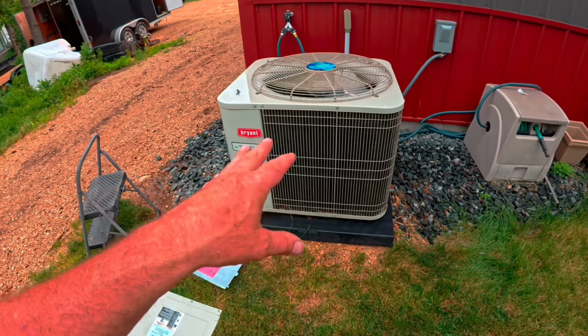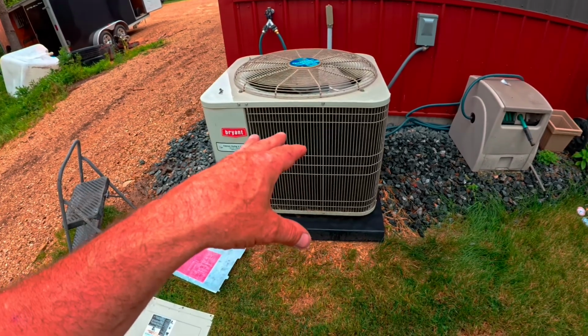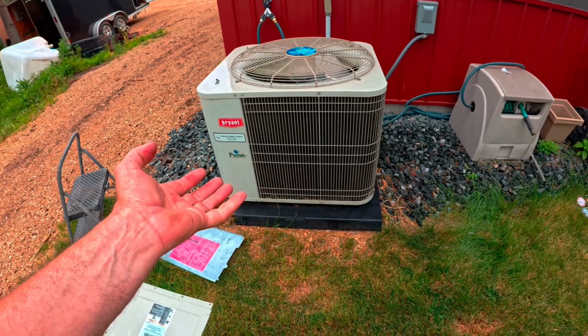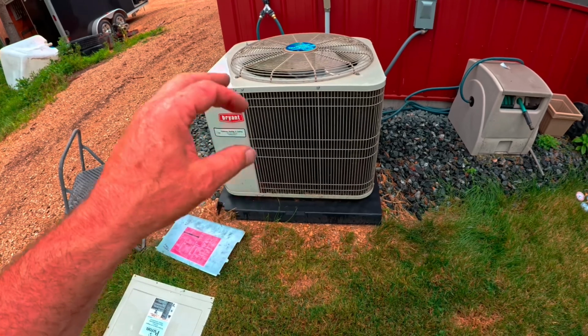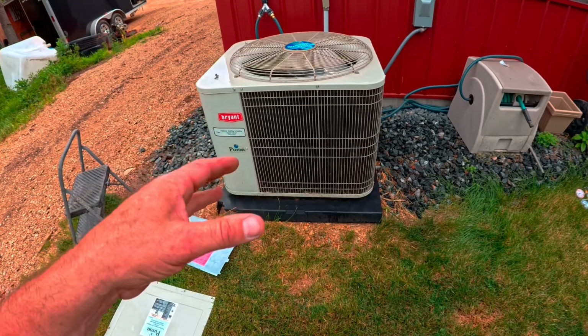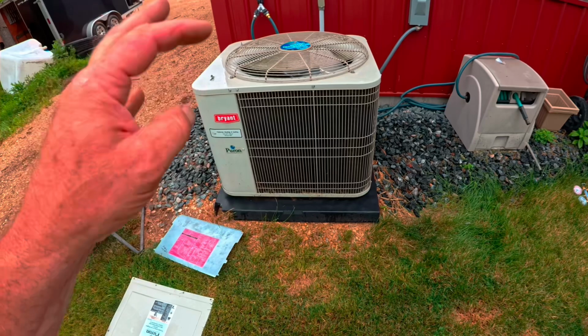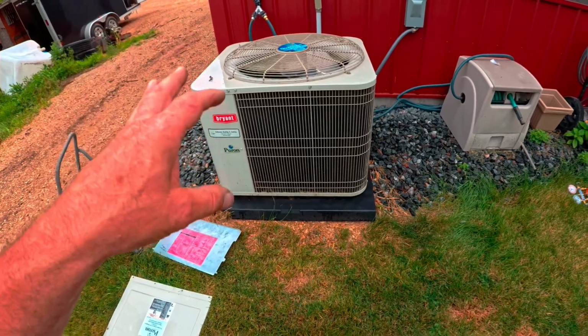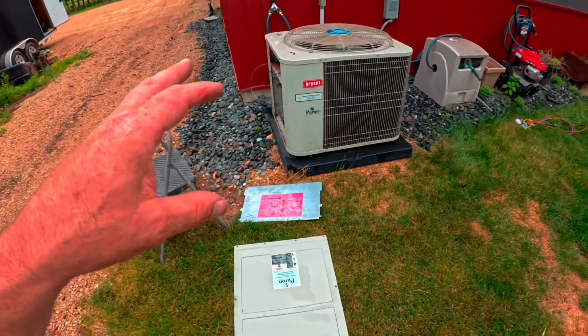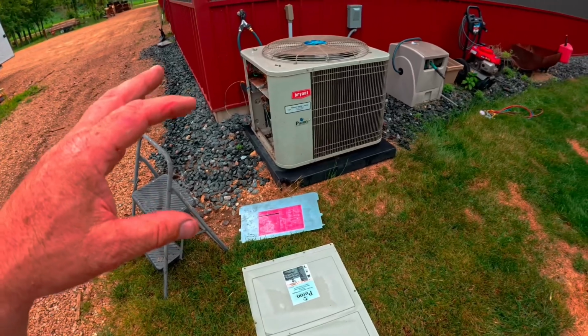If your compressor is not starting and you replace the capacitor and it still won't start, you're going to need to call a technician. At that point, you might need a new air conditioner. But call a technician. There are kits that they can install called a hard start kit that might get you through for a few more years.